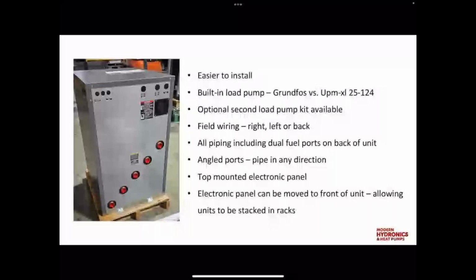The built-in load pump is a Grundfos UPM XL, if you are familiar with their nomenclature, a 25-124 pump. And we do have an optional second load pump kit available if that's required. Having the knockouts for electrical to come into the unit on the right, left, or the back makes for really nice, clean installs, and opens up a lot of flexibility to make this unit fit in all situations. Because of the pipe layout across the back, you can pipe up, down, left, right pretty easily, and it makes for really clean installations.